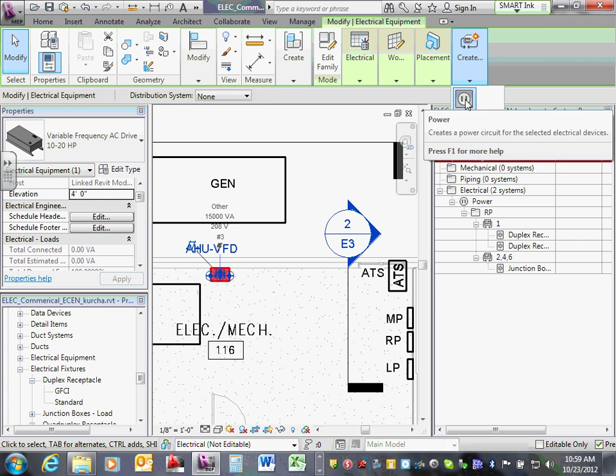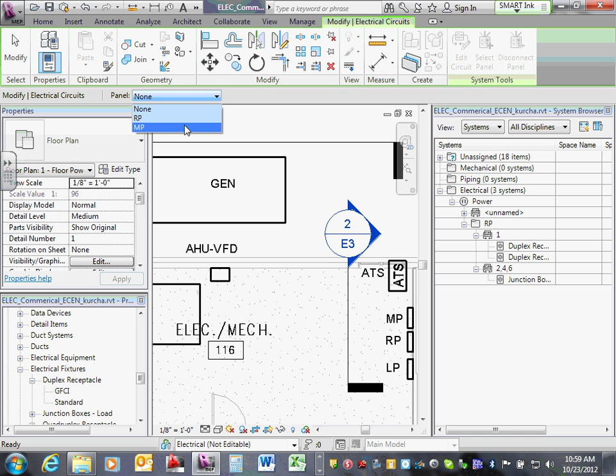Okay, pick the VFD and hit create power. Everybody there? Click on power. When you create power, it says select the panel, will you? Select the panel, I select the panel. Click over here. Oh, by the way, when you select the panel, you can touch the panel, or the easiest way is to come over here. I have two options: I can put it in a receptacle panel or main panel. Which one do you think I have to do based on the criteria? Main panel. And guess what, gentlemen, my VFD has been assigned a circuit.